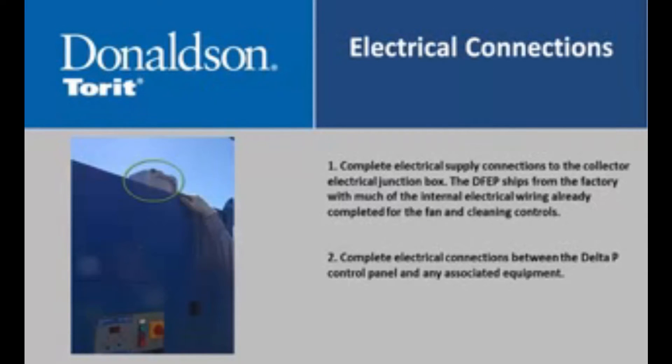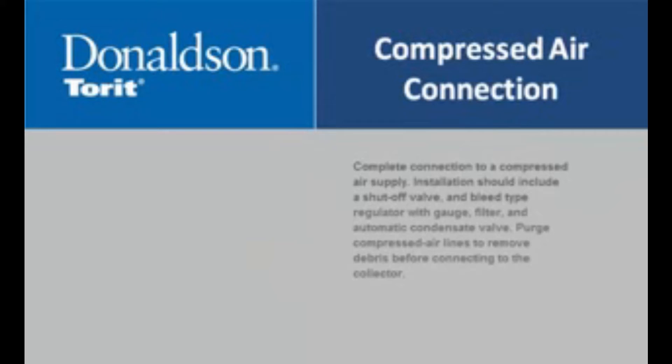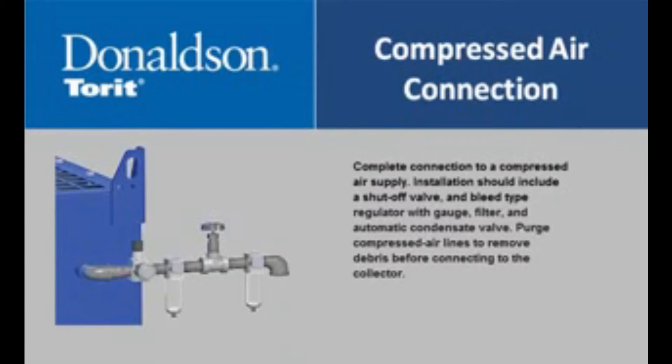Complete electrical supply connections to the collector electrical junction box. The DFEP ships from the factory with much of the internal electrical wiring already completed for the fan and cleaning controls. Complete electrical connections between the Delta P control panel and any associated equipment. Complete connection to a compressed air supply. Installation should include a shut-off valve and bleed-type regulator with gauge, filter, and automatic condensate valve. Purge compressed air lines to remove debris before connecting to the collector.